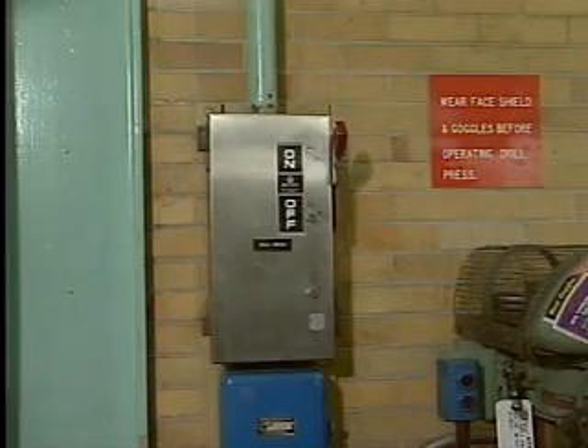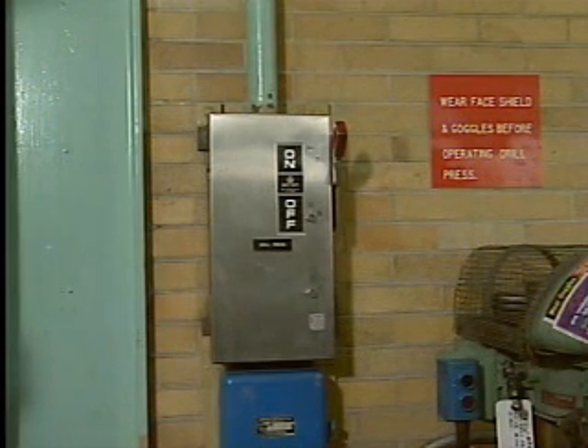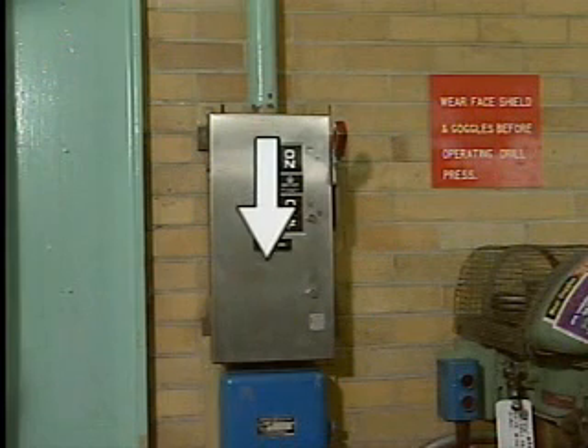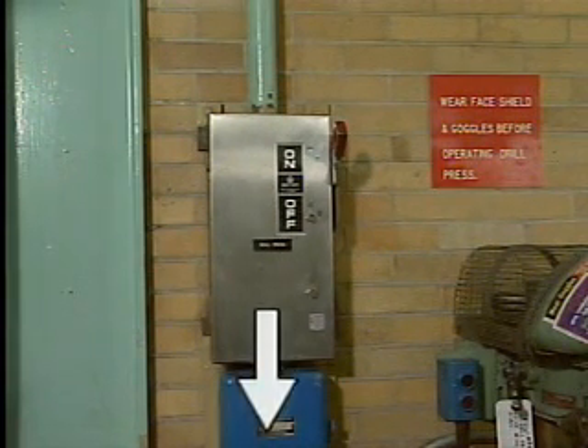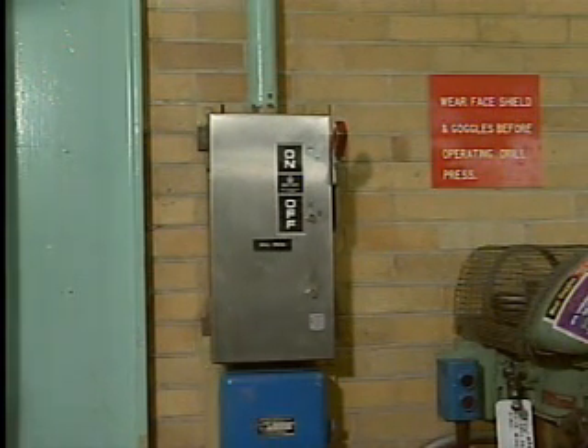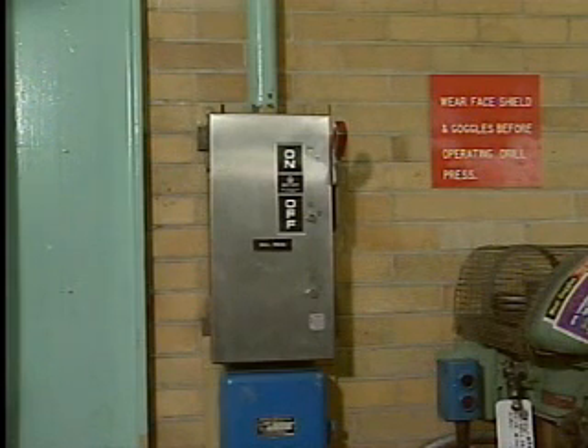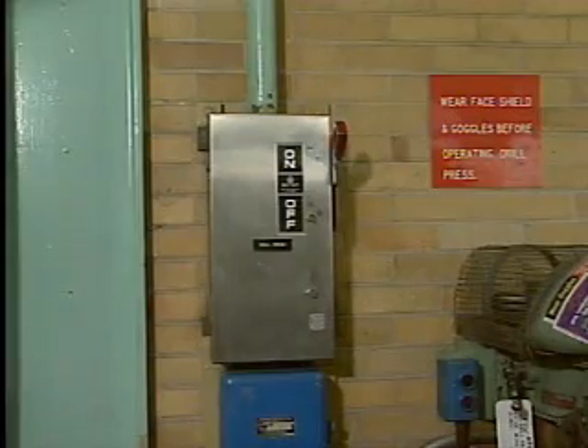Since the electrician has proven that the circuit has the proper operating voltage, he can eliminate the wiring leading into the fuse box, the components in the fuse box, and the wiring leading out of the fuse box into the control cabinet as possible causes of the problem. Also, he can eliminate the possibility that the power for this circuit has been shut off elsewhere in the plant.